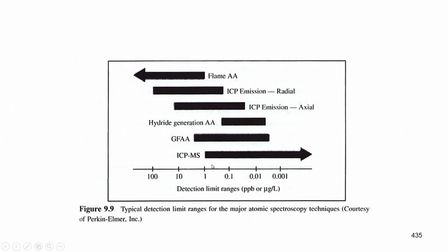That is actually a theoretical limit of signal handling, but the determination limit would be approximately 100 times more than this. Similarly, for ICP the detection limit is about 0.8 ppb, and it can handle up to 100 ppb.